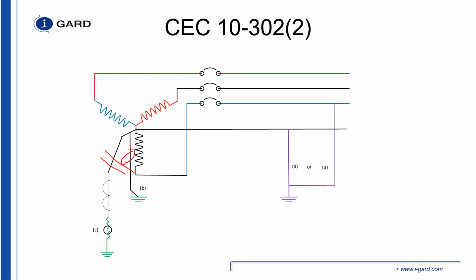The asker also said that he wants to note that the reactor was specifically required by the LDC to reduce or mitigate TOV on the system. I'm not sure if that changes anything. I understand why they use a reactor, but it doesn't comply with the electrical code, and that's unfortunate, because I don't think when they put the code in the CEC, they considered reactors. Right now, reactors unfortunately fall into that. You can probably write to CSA and have them reconsider this for the next code revision. 2021 is probably going to be too late to make any changes, but 2024. Because I think it is important.